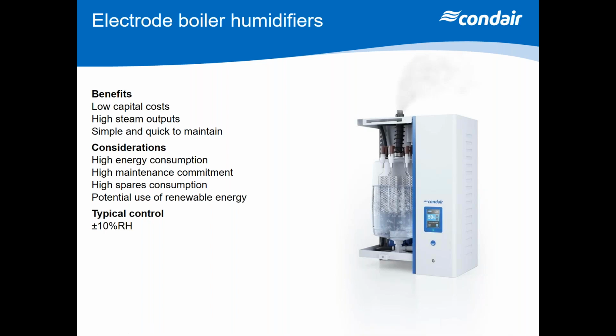The next thing they tried to do was they tried to install, in fact they did install, a reverse osmosis water treatment plant. Now, a reverse osmosis water treatment plant is going to take 97–98% of the minerals out of the water. Great. I never have any minerals forming in my cylinder. The downside is if you feed an electrode boiler with RO water, you'll never produce any steam because if you take the minerals out of the water, it won't conduct electricity.